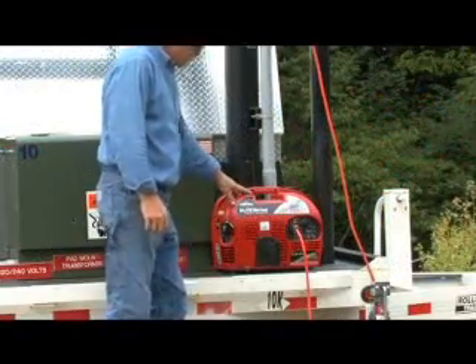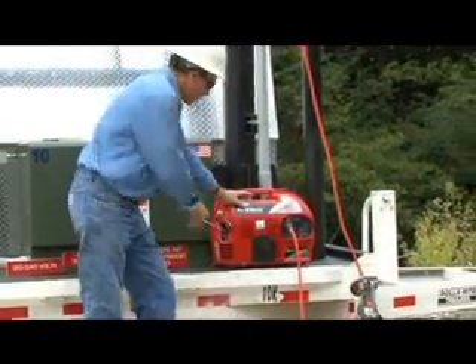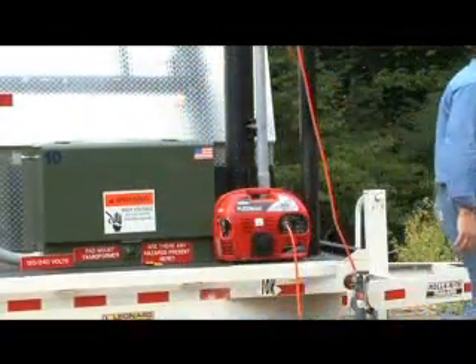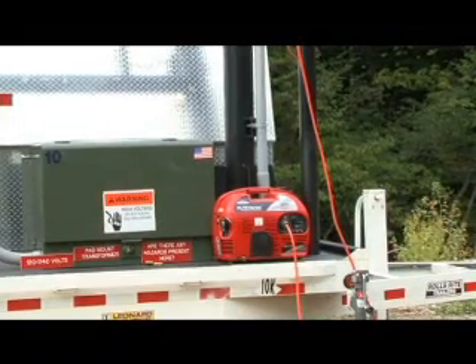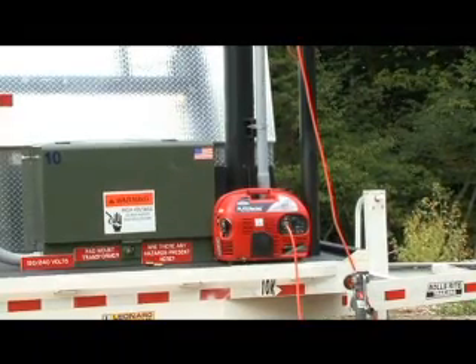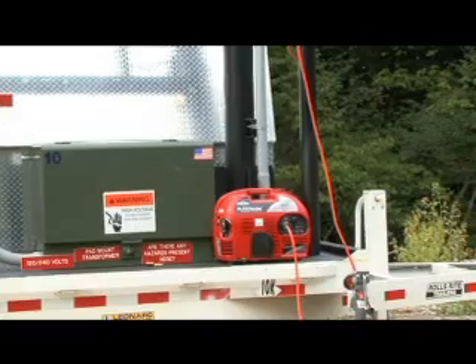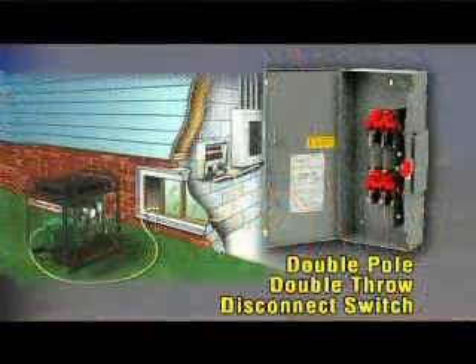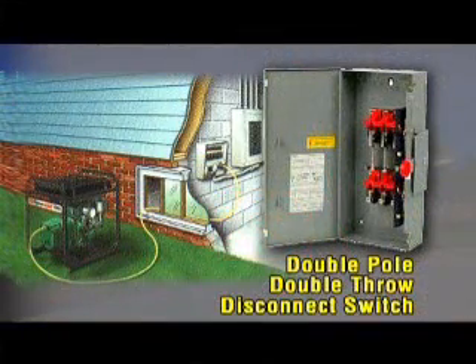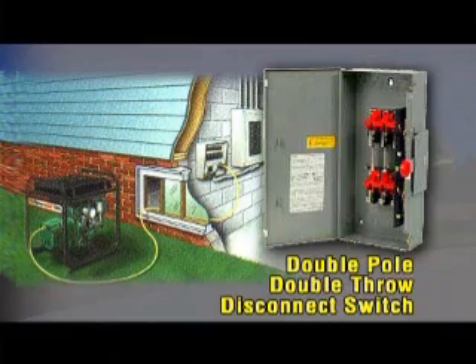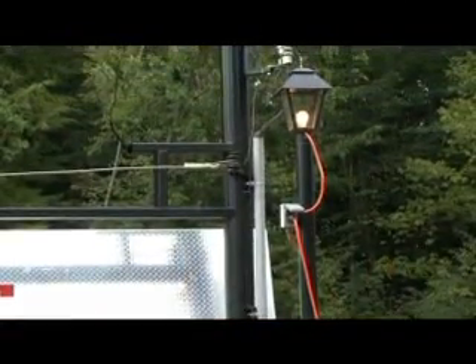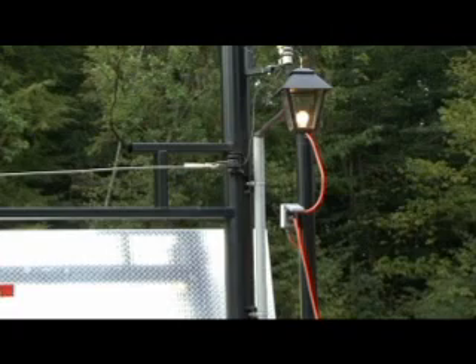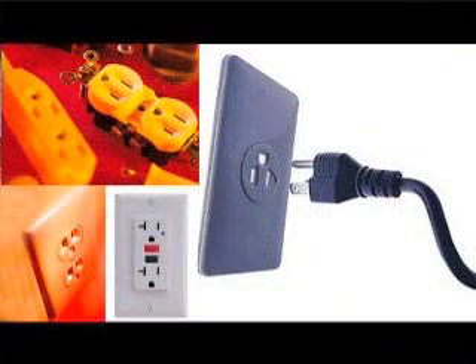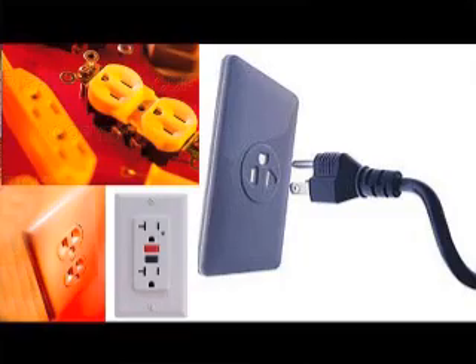Portable generators, such as this one, can pose a serious threat to our line workers when installed improperly. In this demonstration, a portable generator is improperly connected to the trailer. By this, we mean it is not connected to a double pole, double throw disconnect switch as required by the National Electric Code. As you can see, the portable generator is supplying power to a receptacle on the trailer, which represents any receptacle in a home.